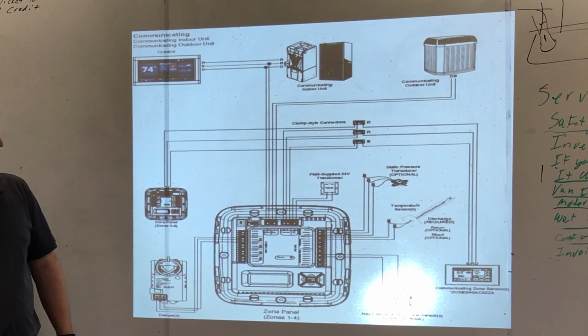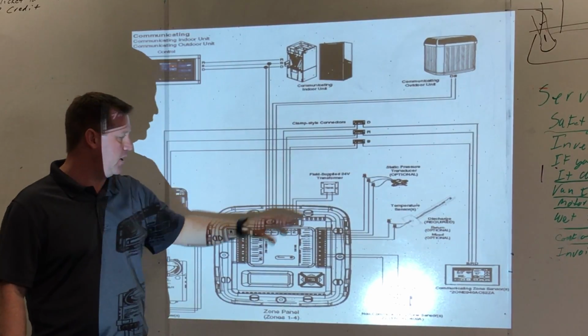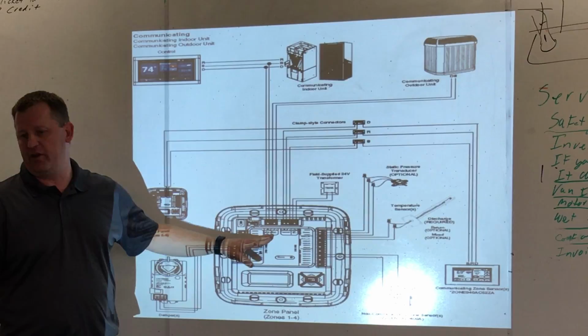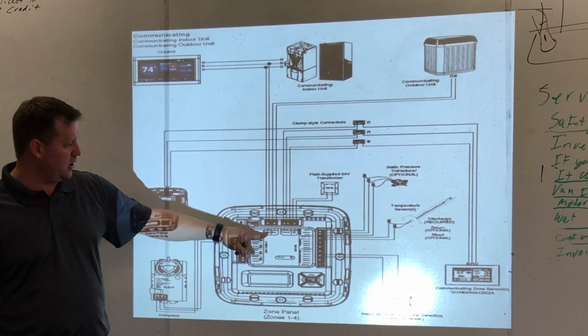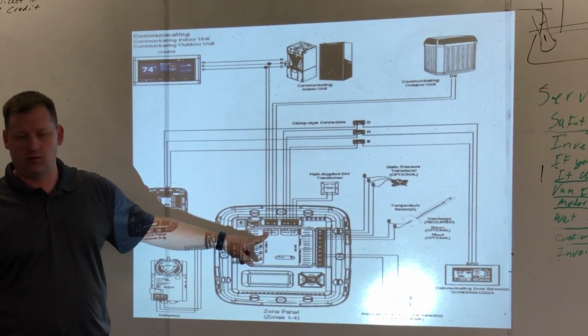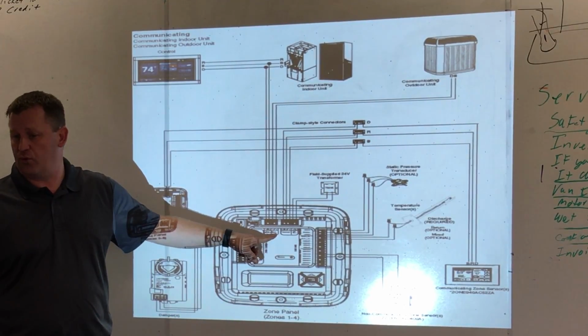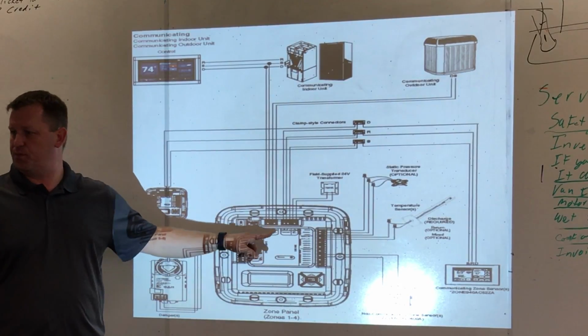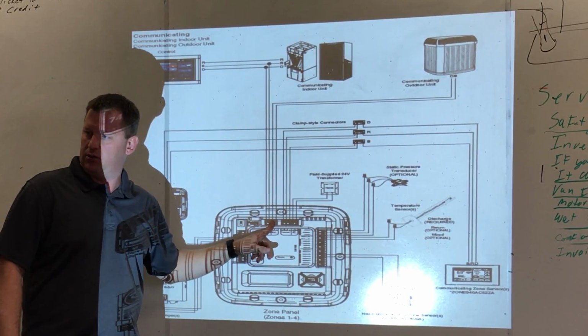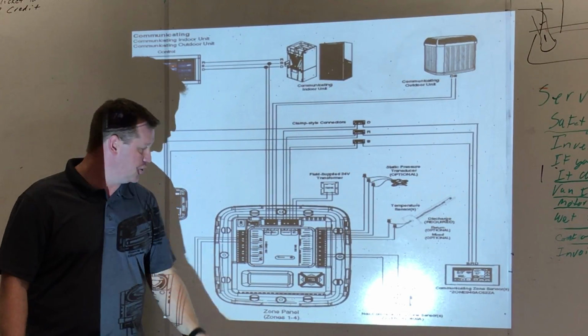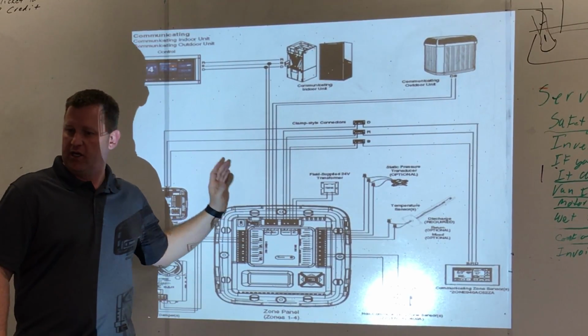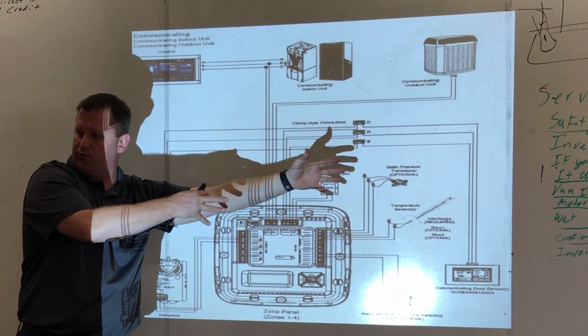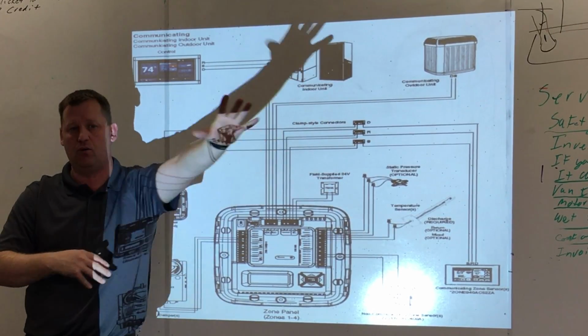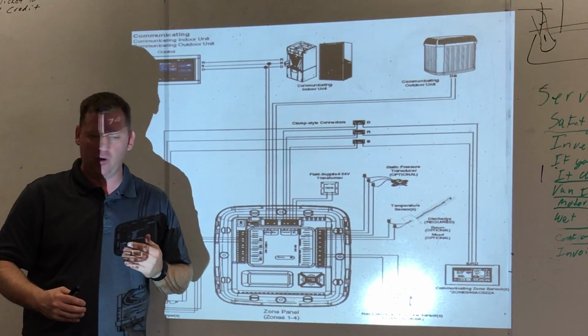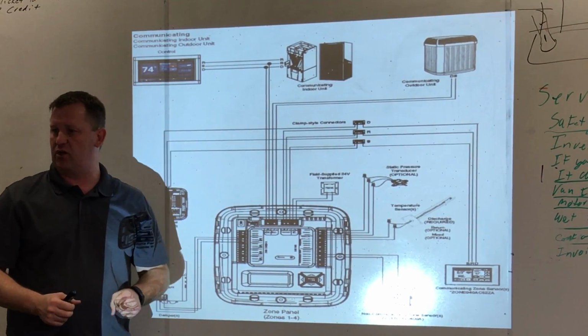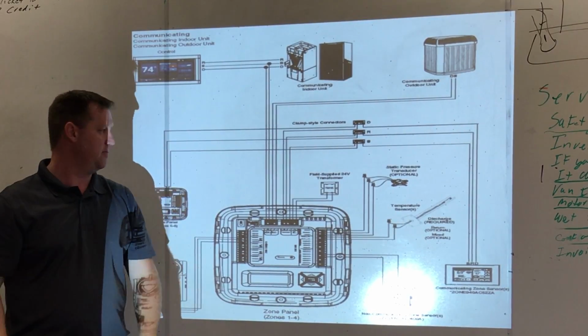What I want you to notice here is follow the wiring laid out for this, because it tells you relay panel or indoor unit, outdoor unit, communicating outdoor unit. Follow those, because later on if we have to troubleshoot a problem with the communication cycle, we can disconnect a D-wire here, kill everything this way, and check voltage at the indoor unit to decide if the problem is here or there — it helps with troubleshooting. Whereas if you bring everything in and just wire nut everything, now you've got to start breaking wire nuts apart.